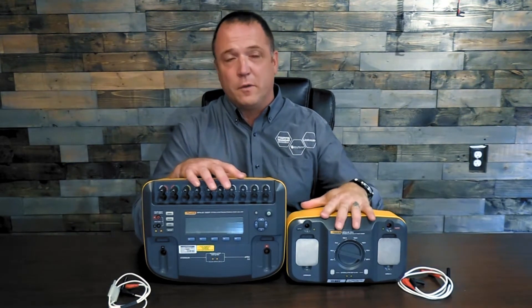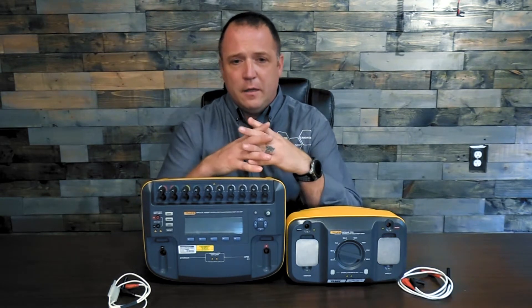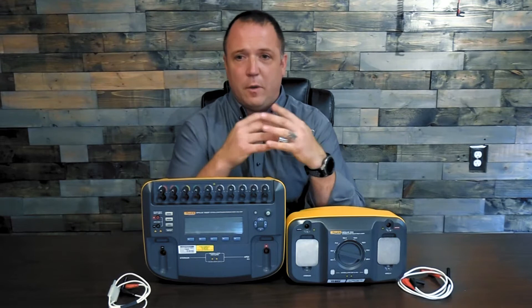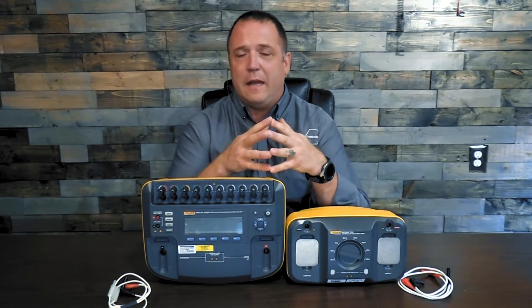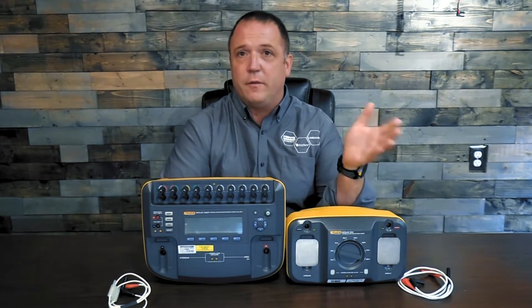Hello, I'm Justin Ross with Fluke Biomedical and I'm coming back to talk to you a little bit more about transthoracic impedance and testing defibrillators at different ohm loads. We've presented this concept a few times in our best practice videos and webinars, and the question gets brought up: okay, this is great, but why do I need to test this? It's been written into the IEC standards for years, and as defibrillators are developed it's something tested in the factories.